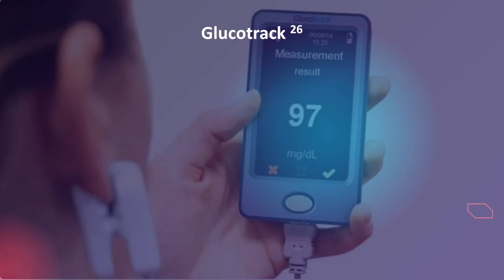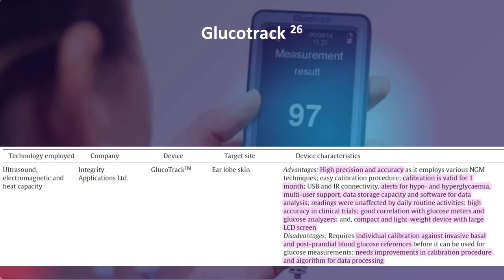GlucoTrack is a device that contains an ear clip to measure glucose levels non-invasively via the earlobe. The reason behind selecting the ear as a site of monitoring is that it is easily accessible with high blood supply. This table summarizes some information about the device.